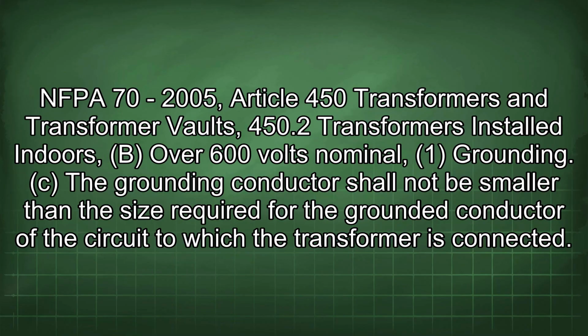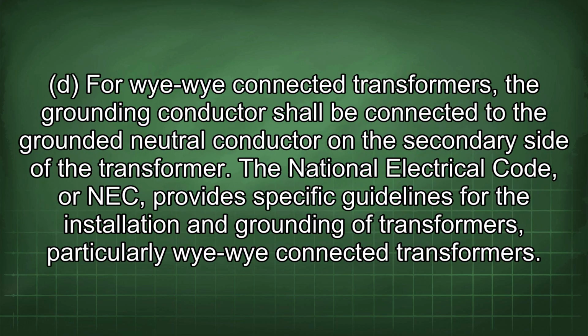NFPA 70-2005, Article 450 Transformers and Transformer Vaults, 450.2. Transformers installed indoors, over 600 volts nominal, 1 grounding. C. The grounding conductor shall not be smaller than the size required for the grounded conductor of the circuit to which the transformer is connected. D.